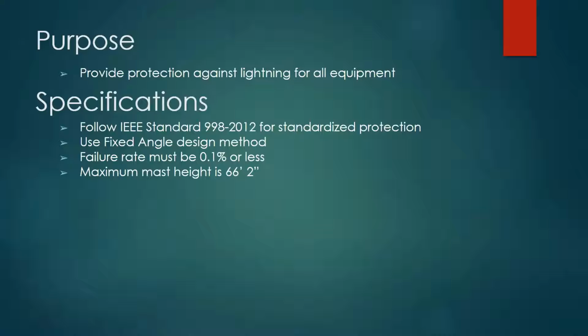Hi, my name is David Sikora, and I will be going over our lightning protection. So the purpose of our lightning protection was to provide protection against any electrical surge that our substation might experience. Some specifications we had to follow. We had to follow the IEEE standard for direct stroke lightning protection for substations. We had to use the fixed angle design method because this was what our sponsors were most familiar with. The failure rate was to be 0.1% or less, and the maximum mast height was 66 feet and 2 inches as designated by our sponsor.